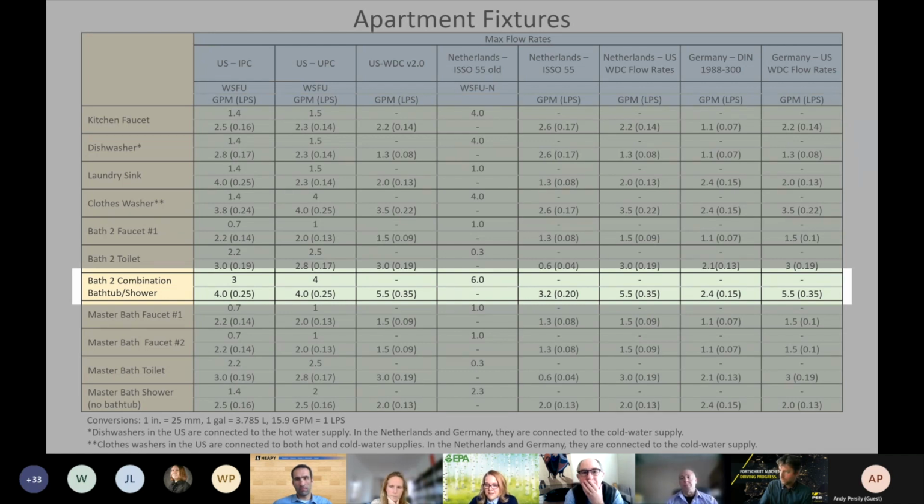There's one question for the chat that is asking about the peak demands. So we're making some assumption about peak demand flows, but what is the period that we're assuming for how long you're at that flow? So is it for a few seconds or some other duration, or does that vary by approach? Speaking again for the water demand calculator, when we're estimating the 99th percentile, that's at an instant of observation.